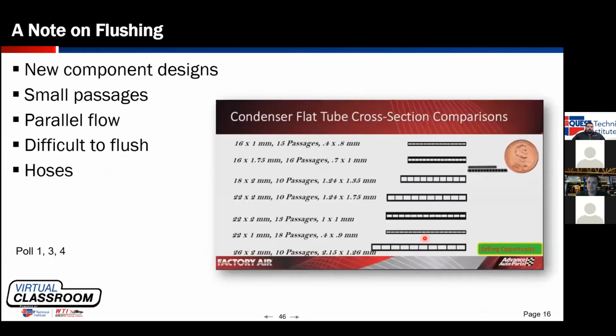One note on flushing components. As systems have gotten more and more efficient, the condenser passages have gotten smaller and smaller. You can see the passages at the top of this screen are 0.4 millimeter by 0.8 millimeter. I have some condenser cross sections that are even smaller than that. These are very, very difficult to flush, if not impossible. So be aware of that.